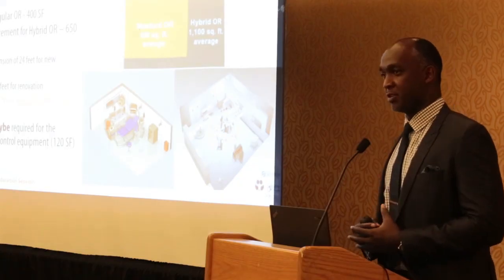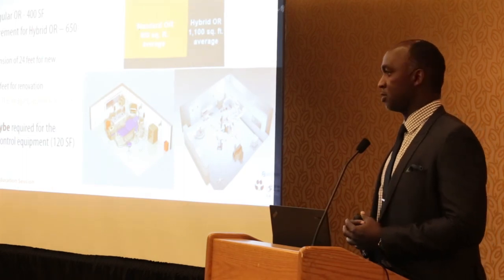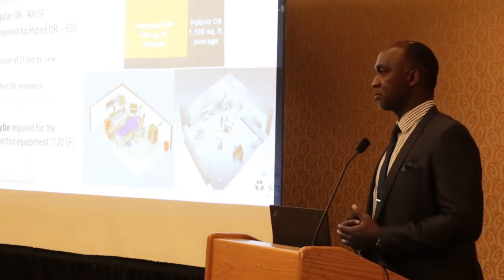The minimum size of a hybrid OR by the guidelines also says 650 square feet, which talks about 24 feet if it's a new OR, or 22 feet if it's a renovation. I've never seen a hybrid OR at 650 square feet. It's always twice the size. And there's a caveat that says it depends on the imaging equipment that's installed. They're usually huge. If it's an MRI, if it's a CAT scan, they're huge. It's a lot of space.